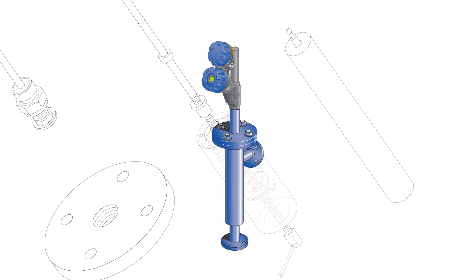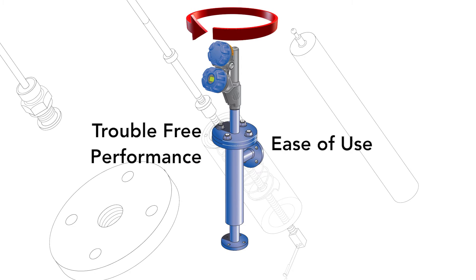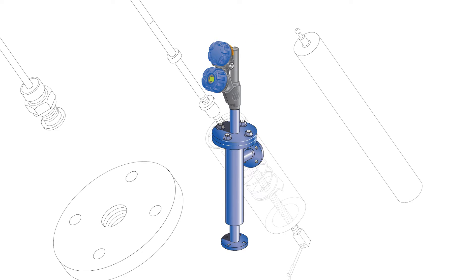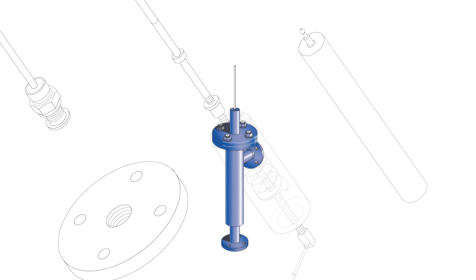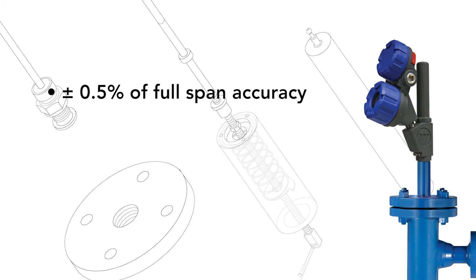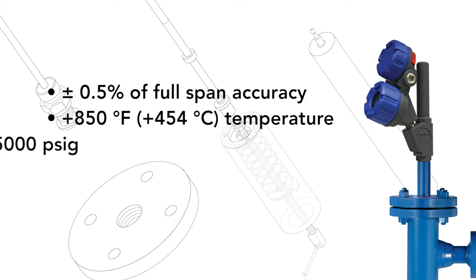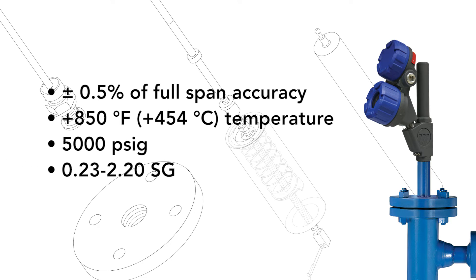The robust design of the E3 Modulevel displacer transmitter ensures reliable, trouble-free performance and remarkable ease of use. A 360-degree rotatable head allows for easy wiring. The head can be removed without depressurization of the process or chamber to enable fast, easy maintenance. The E3 Modulevel also features plus or minus 0.5% accuracy of full span, with temperature, pressure and specific gravity capabilities of plus 850 degrees Fahrenheit, 5000 PSIG, and 0.23 to 2.20 SG respectively.